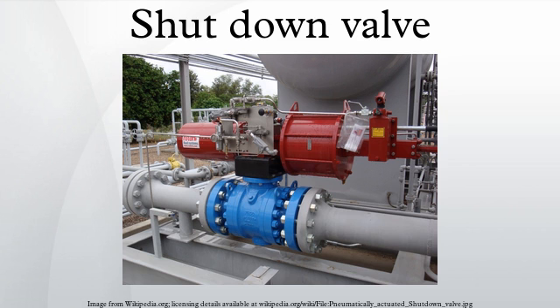In order to adhere to this level of performance, it is necessary to test the valve. There are two types of testing methods available: proof test, a manual test that allows the operator to determine whether the valve is in the as-good-as-new condition by testing for all possible failure modes and requires a planned shutdown; and diagnostic test, an automated online test that will detect a percentage of the possible failure modes of the shutdown valve. An example of this for a shutdown valve would be a partial stroke test.